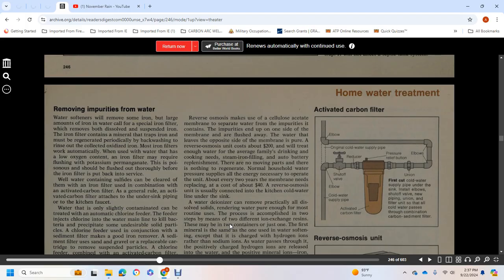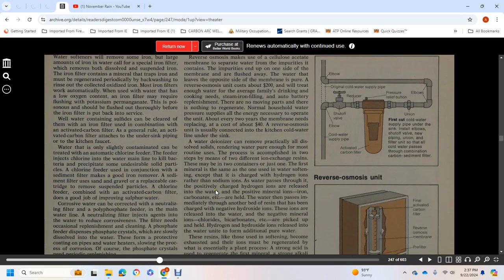It will treat enough water for the average family's drinking and cooking needs, steam iron filling, and automobile battery replenishment. With no moving parts and no need to regenerate, it uses normal household water pressure as the energy necessary to operate the unit. About every 2 years the membrane needs to be replaced, at a cost of about $40. A reverse osmosis unit is usually connected to a kitchen cold water line under the sink.